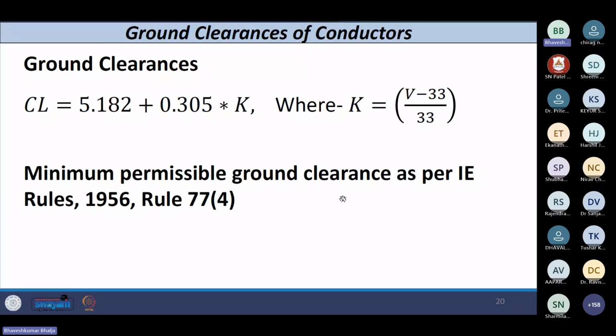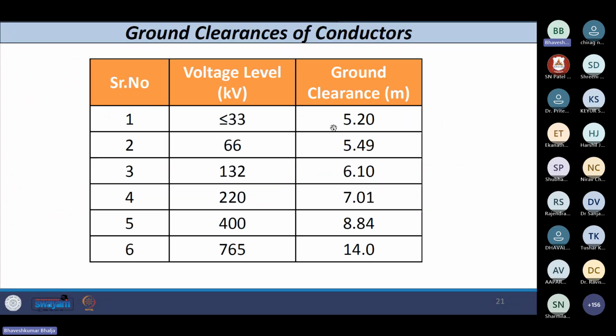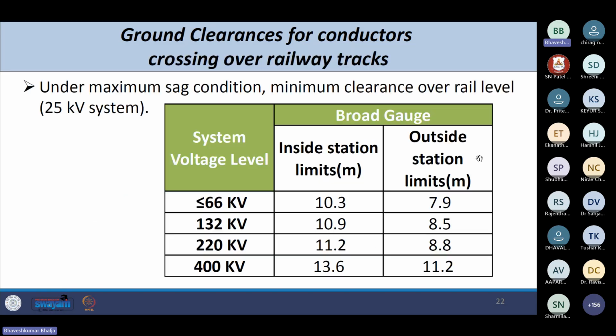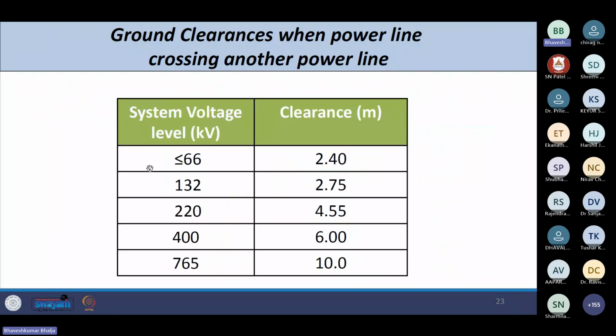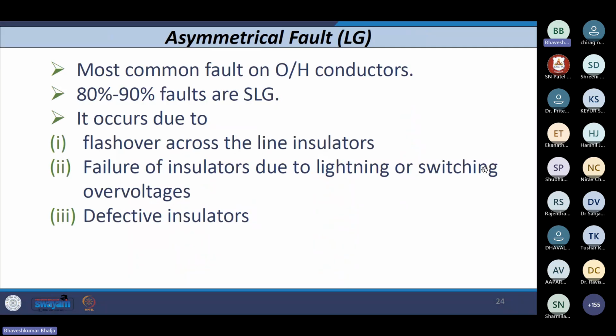Then comes ground clearance, which also plays an important role. In the Indian system, as per IE Rules 56, Rule 77 by 4, the ground clearance depends upon the voltage level. For 400 kV, the ground clearance is close to 9 meters, and for 765 kV it is close to 14 meters, which is also very high. If you have railway tracks, you can calculate the ground clearance using different formulas. I am not going into that detail because I hope it is already known.